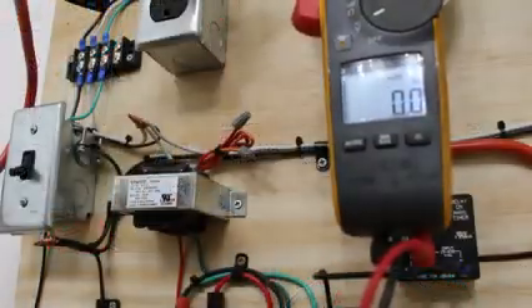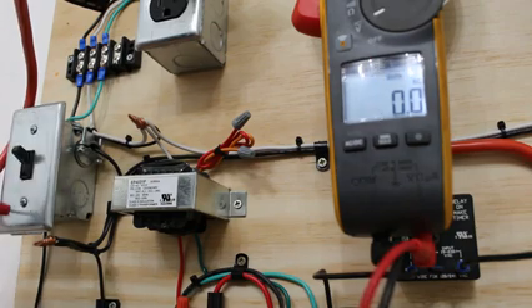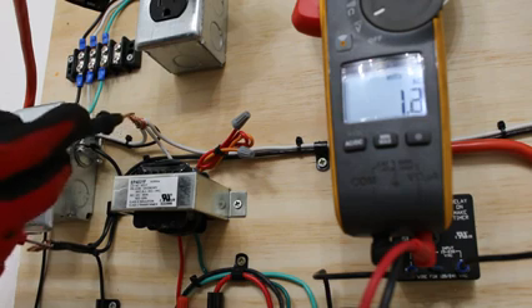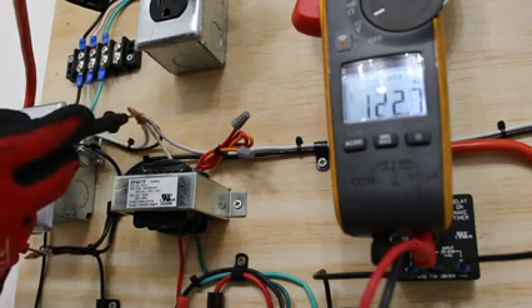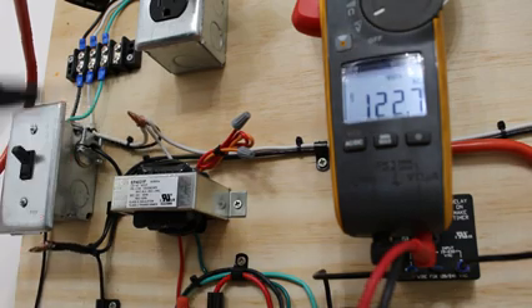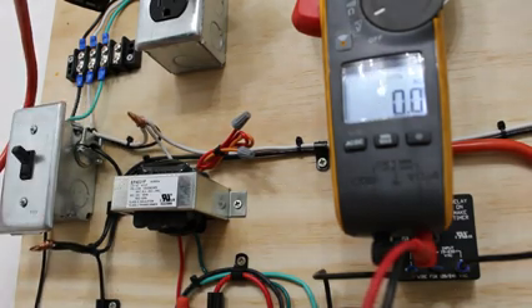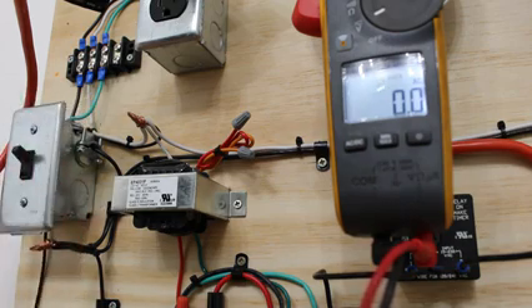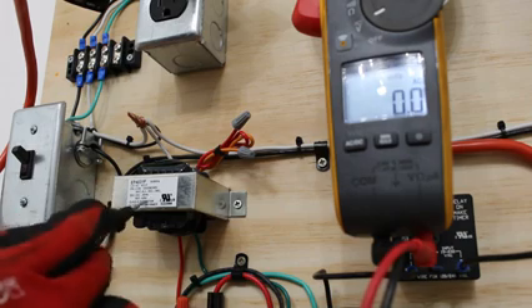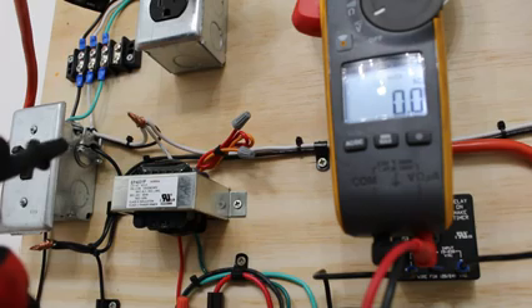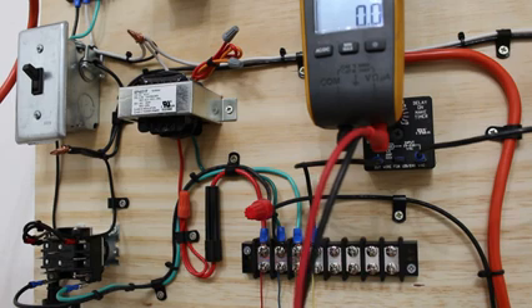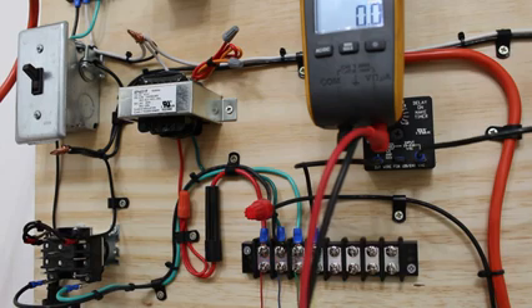All right, so we have our meter set to volt AC. I'll turn the power on. Between black and white, we should have 120. Right there, as you can see, we have 122 volts, indicating we have our 120. So let's say if we had any of these primary voltages and we didn't have 24 volts, then your transformer is bad. But before you say that, pay attention to your transformer. Sometimes there's a built-in breaker inside, and sometimes there is an inline fuse connected. So we have 120 volts at our primary, and then we checked at our thermostat, we had our secondary. Of course, in this case, everything is good.